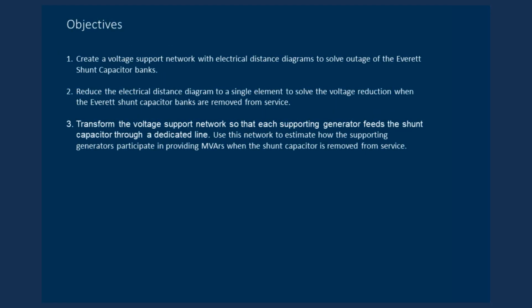In this next segment, we'll be building an equivalent circuit to study the outage of the Everett shunt capacitor. We'll have three objectives. We'll create a voltage support network with electrical distance diagrams to solve the outage of the Everett shunt capacitor banks. We'll reduce that electrical distance diagram to a single element to solve the voltage reduction when that shunt capacitor is removed from service. We'll also transform the voltage support network so that each supporting generator feeds the shunt capacitor through a dedicated line. We can then use this network to estimate how the supporting generators participate in providing megavars when the shunt capacitor is removed from service.